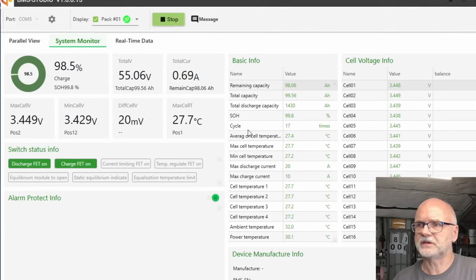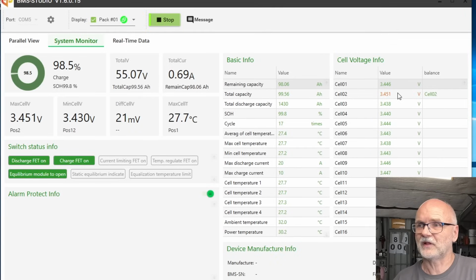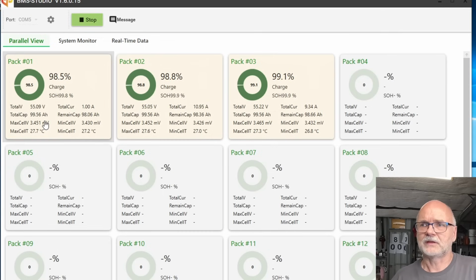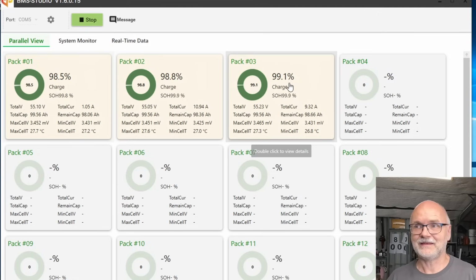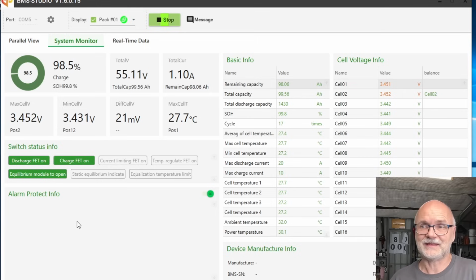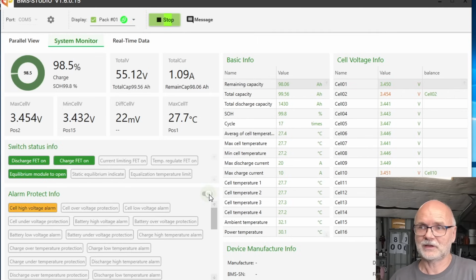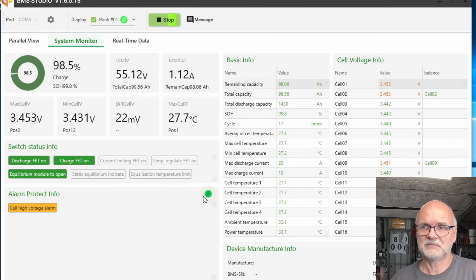We've definitely reached the 3.45 volts with some of the cells. You can see the balancer kicking in, the passive balancer. We've got 20 millivolt deviation, it's not too bad. And as you can see, we are still showing 98.5, 98.8 and 99.1%. So we are getting somewhere. None of the batteries is actually showing an alarm. Only if you click on this icon, we can see a cell high voltage alarm. But for some reason, it doesn't show.